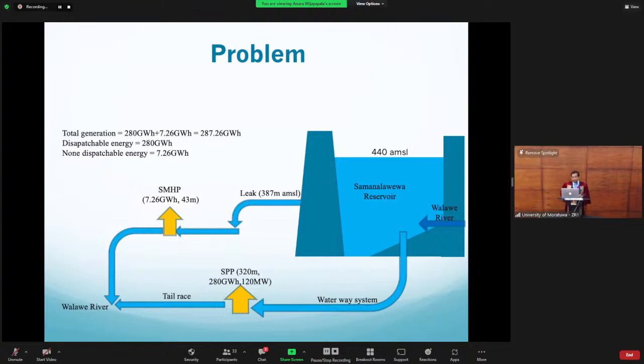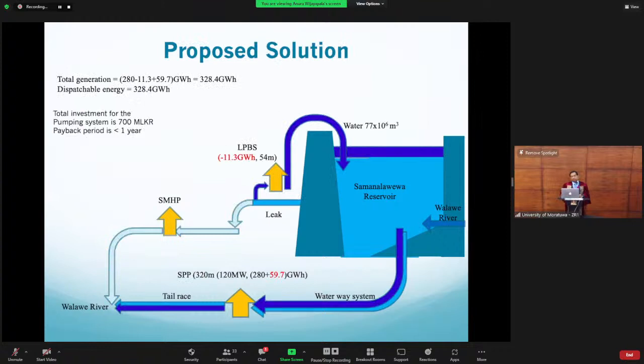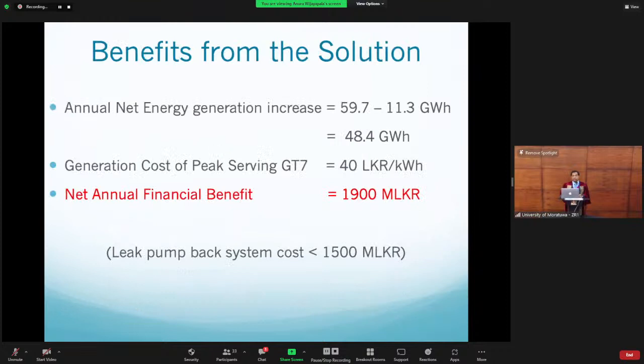So we did the calculations. We designed the leak pump back system, and then looked at how much energy is required to pump water back to the reservoir. But we can't pump back all the water. We have to let the irrigation water flow through the Walawe River. So subtracting the minimum water requirement of the river, we decided to pump back the balance, for which we need 11.3 gigawatt hours, so 11.3 million units. And then the same water, when it runs to the power plant, as you can see in the bottom there, can produce 59 or approximately 60 million units. Which means we can have an excess of 48 gigawatt hours if we do this.